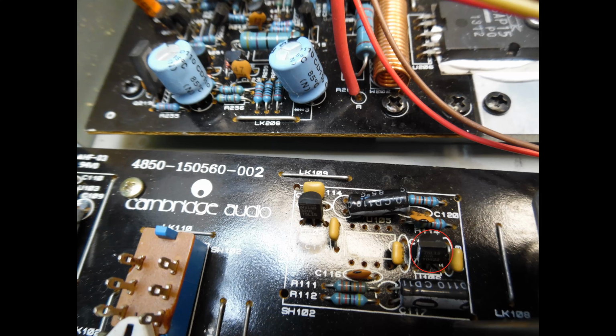So I replaced both of the voltage regulators and then retested, and I had positive 15 volts, no high voltage at all. But because these two operational amplifiers had been overdriven in terms of power supply voltage, I simply replaced them. I didn't want to take the risk that the op amps had been damaged. So once I replaced those, and of course also the 500 milliamp 15 volt positive regulator, there was no issue with the performance of the amplifier.